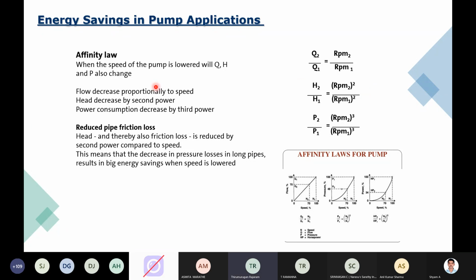You have this point: the flow decreases proportionally to speed, the head decreases by the second power, and your power consumption decreases by the third power. So this is your true impact, which helps you save a lot of energy whenever you want to operate the pump at lean loads, rather than adopting the other options like control valve or bypass valve or other situations.